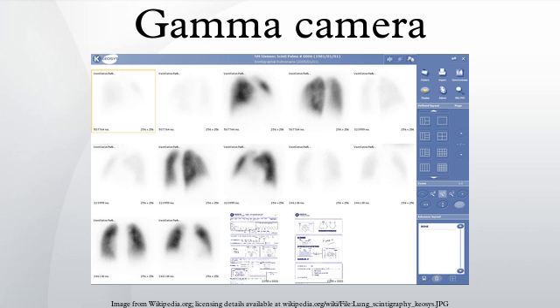SPECT imaging, as used in nuclear cardiac stress testing, is performed using gamma cameras. Usually one, two or three detectors or heads are slowly rotated around the patient's torso.